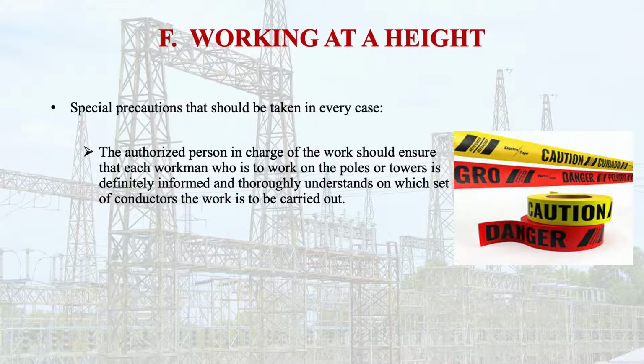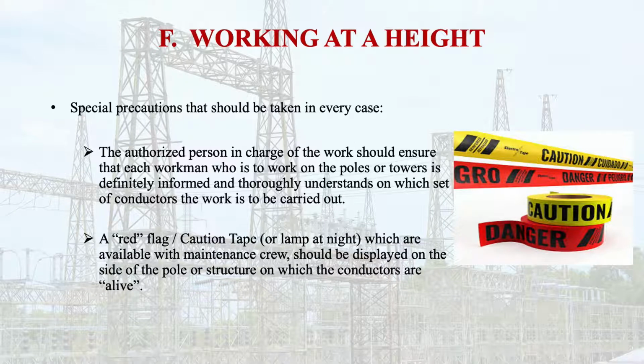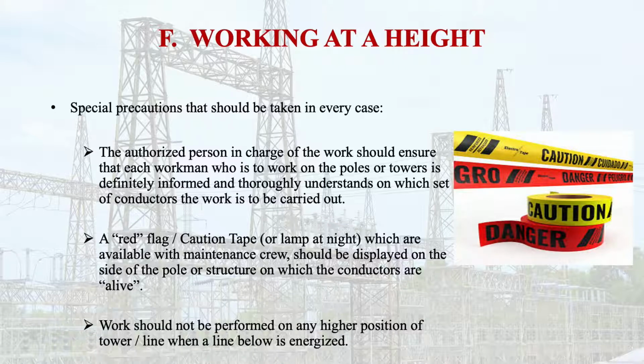What are these? The authorized person in charge of the work should ensure that each workman who is to work on the pole or tower is definitely informed. He should be well informed and thoroughly understand on which set of the conductors the work is to be carried out. A red flag or a caution tape, or a lamp in the case of night, which are available with the maintenance crew, should be displayed on the side of the pole or structure on which the conductors are alive. Work should not be performed on any higher position of tower or line when a line below is energized. Remember this thing.